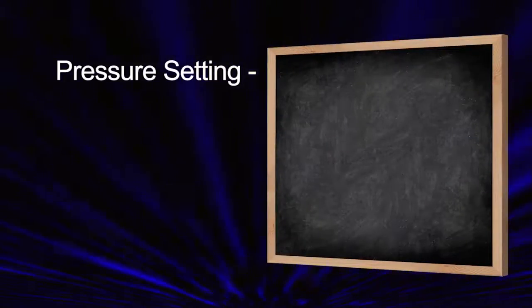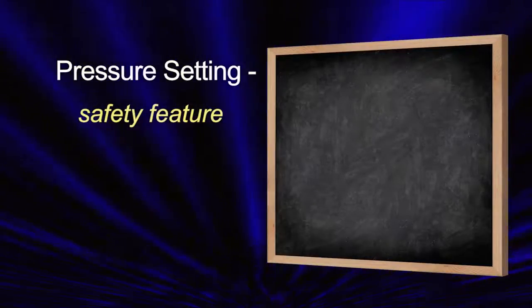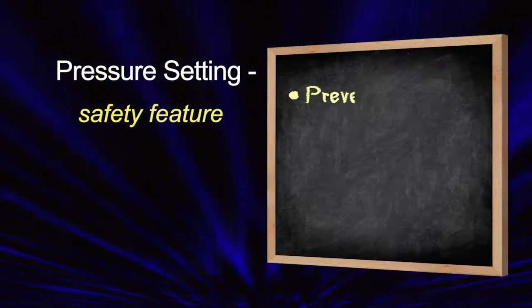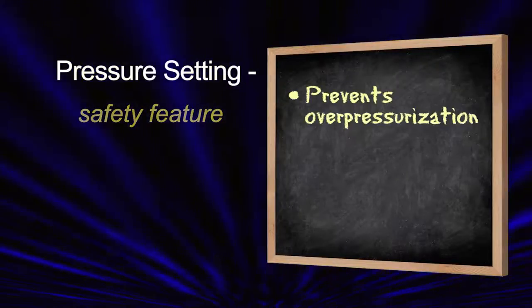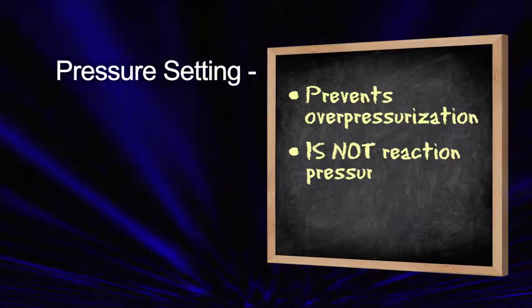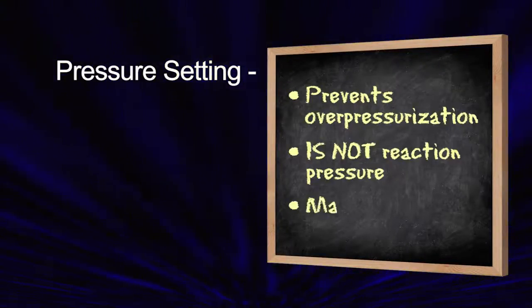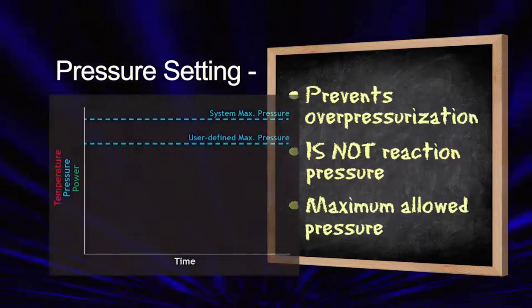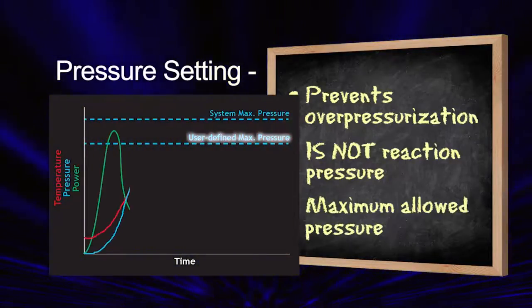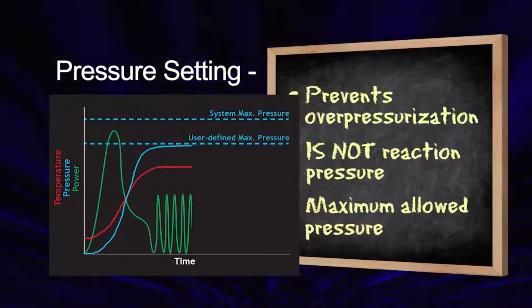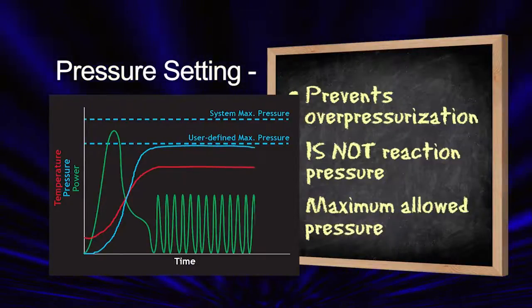Since heating solvents above their boiling points naturally generates pressure, the pressure setting on the Discover serves as a safety feature to prevent over-pressurization events. This is not the pressure at which a reaction will run, but rather the maximum allowed pressure. If the pressure reaches the user-defined setpoint, as shown here, the power will cycle on and off to prevent over-pressurization.